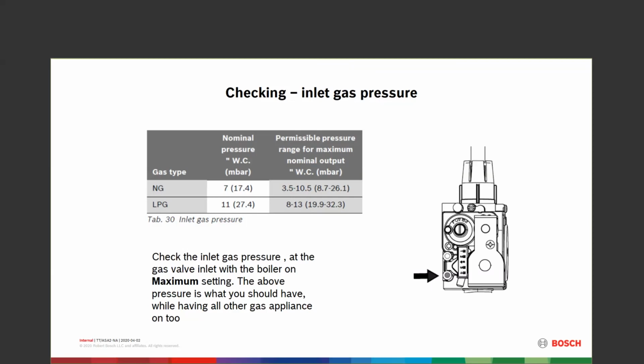So on our Greenstar, what we'd ultimately like to see, or what the Greenstar is ultimately happy with, is 7 inches water column in natural gas and 11 in LP. There are permissible ranges, 3.5 to 10.5 on natural. You cannot drop below 3.5. These won't run. Same with LP, 8 to 13 is permissible. You cannot drop below 8.